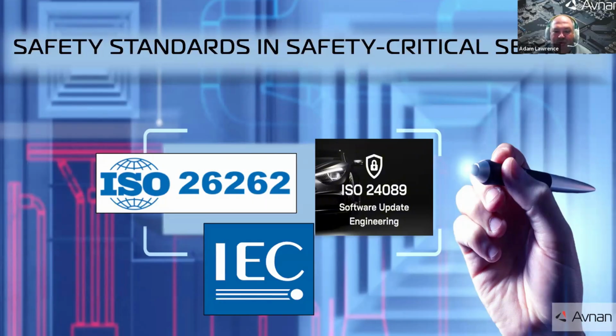Before we look at specific regulations, it's worth stepping back and recognizing that the HVAC industry is taking cues from safety-critical sectors like automotive and medical devices. For instance, in medical and automotive, traceability and self-diagnostics aren't just best practices, they are requirements. Standards like IEC 62304 for medical software and ISO 26262 for automotive electronics enforce strict controls around fault detection, documentation, and safe behavior. The newer ISO 24089 even covers how updates must be engineered and delivered securely. While HVAC isn't as tightly regulated yet, we're seeing a shift towards this level of discipline, especially as systems become more software-driven. For example, today's microcontrollers increasingly perform startup self-checks to verify memory, sensor inputs, and safety paths before allowing operation. That's traceability and diagnostics being baked right into the firmware, just like in a car or a medical device.